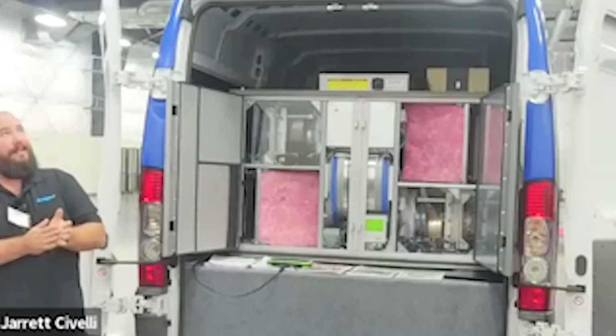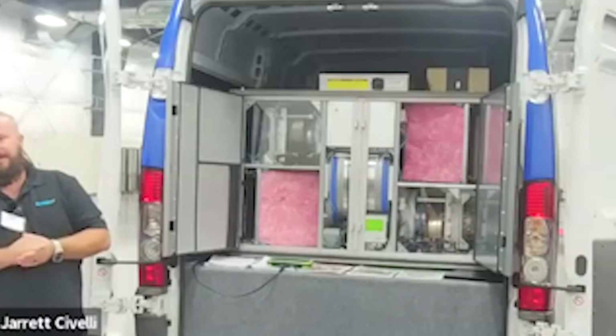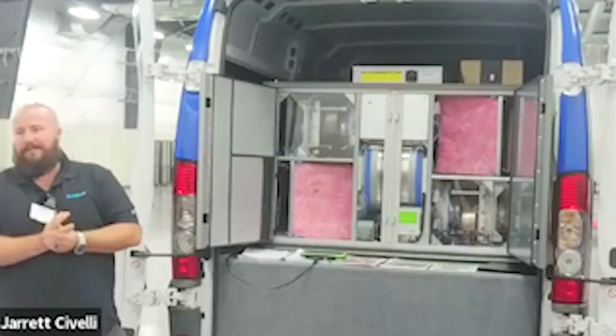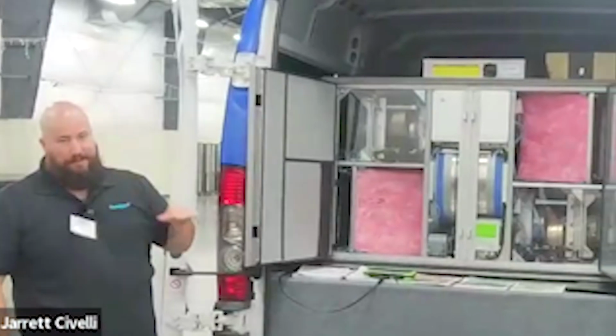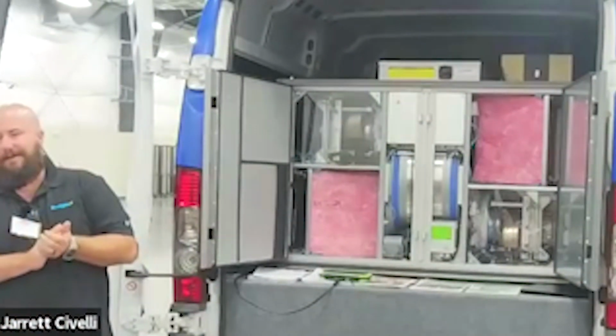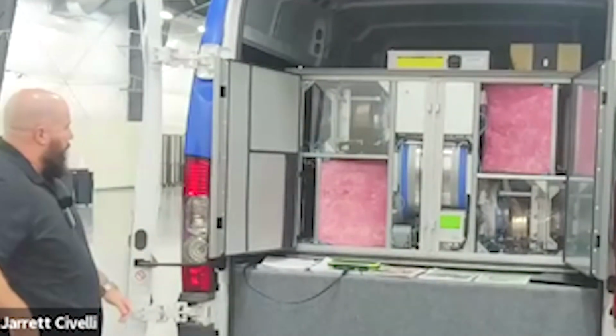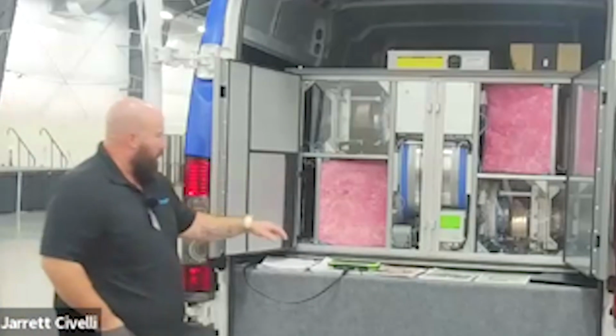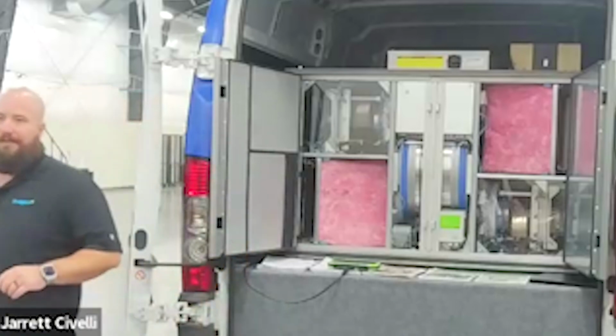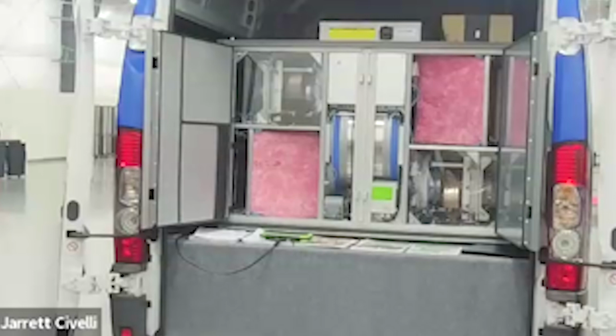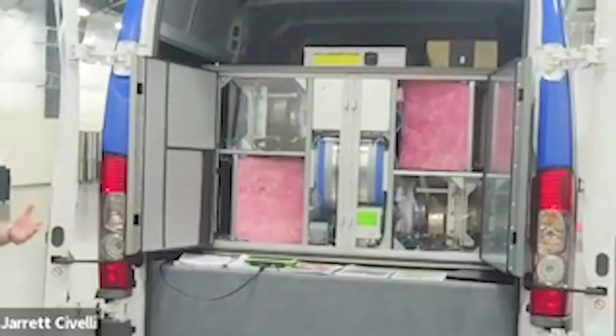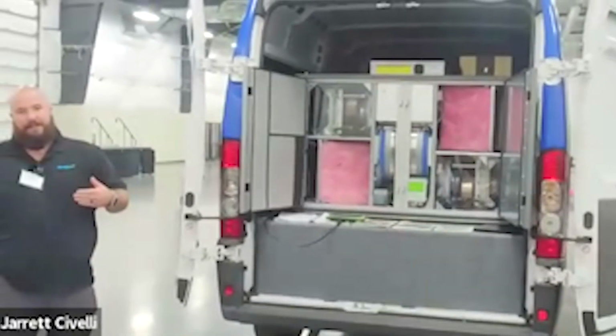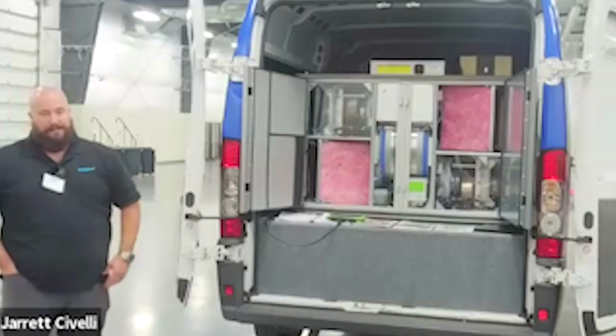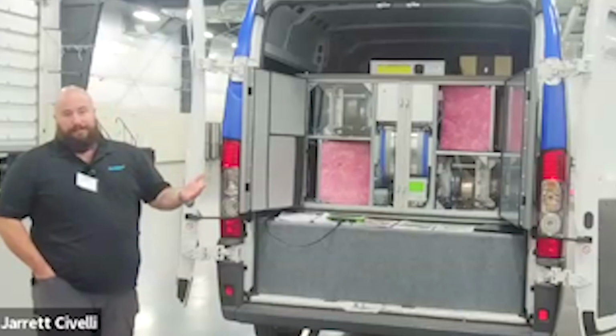Back to wheel efficiency. AHRI 1061, kind of the standard for ERVs, is roughly 60 to 64%. And then your tier 2, that's the 80 to 85% roughly. Swegan advertises their wheel efficiency around 80, but it's typically higher, as high as 85%. One of the big things to get that efficiency is this stepper motor right here, and we're able to get down to 1 RPM. So that wheel is turning extremely slowly so that we can transfer as much energy as possible. Some other manufacturers just use a drive, and those drives can't go down to that low an RPM. They'll maybe drive down to 30% of the motor speed. So it's just one of the added features that gives us that additional efficiency.